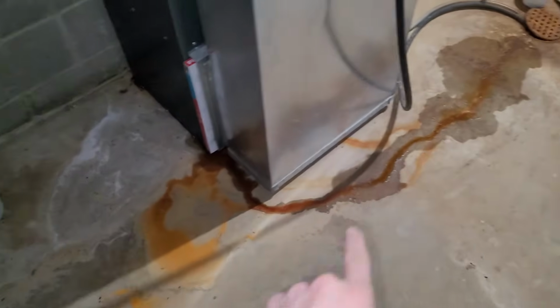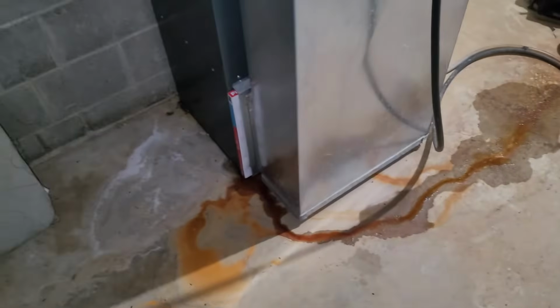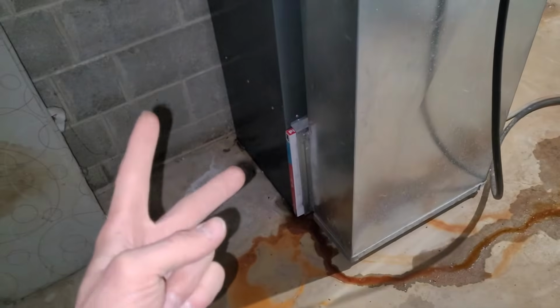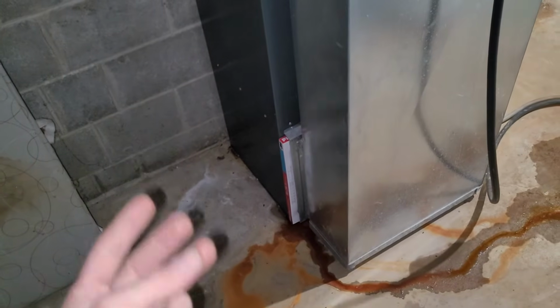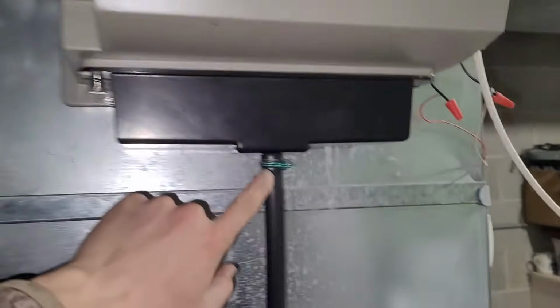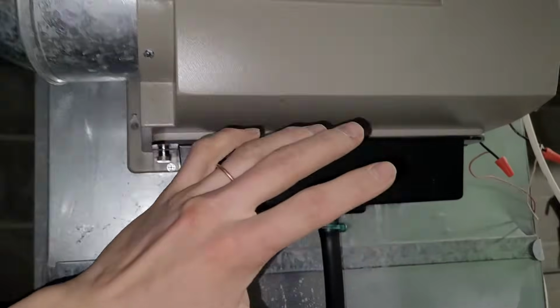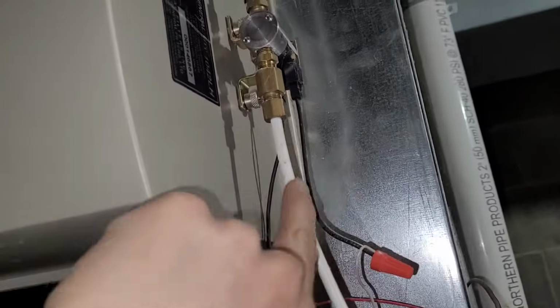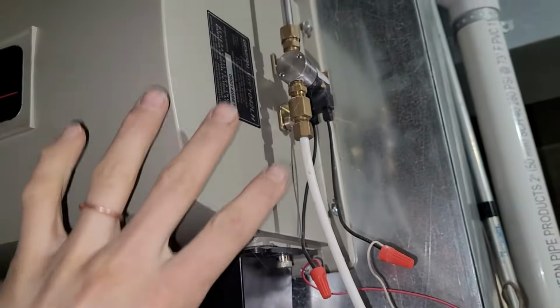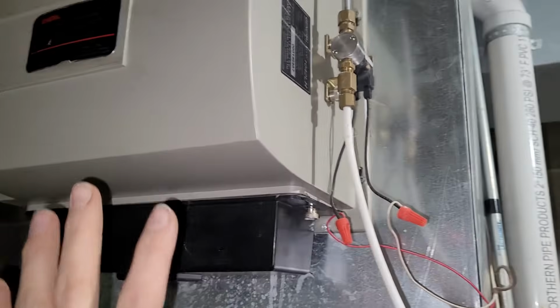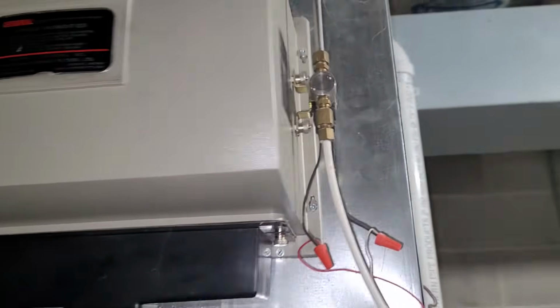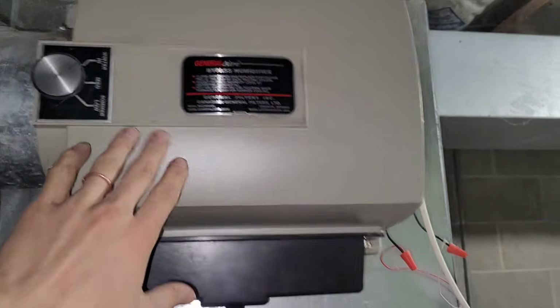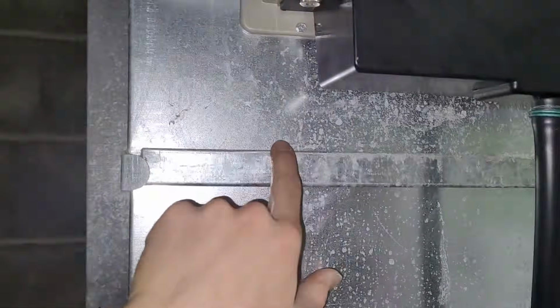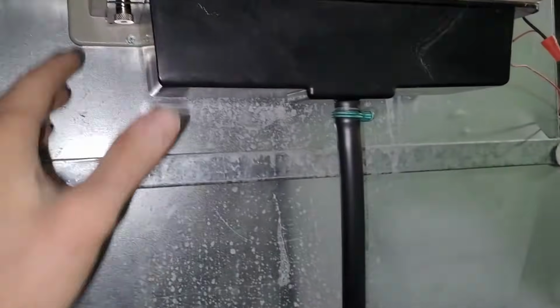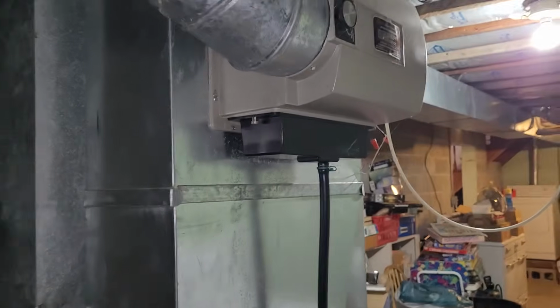So if you have water leaking out around the base of your furnace, it can really only be coming from two main things, well, possibly three. If your system has a humidifier and the drain is plugged on it, or there's actually a water leak on the inlet side somewhere there, you could have some water. That's pretty uncommon. I've really not seen that very many times. But if your system has that, you can check around that, see if there's any water weeping down here or the drain is like overflowing or something on there.